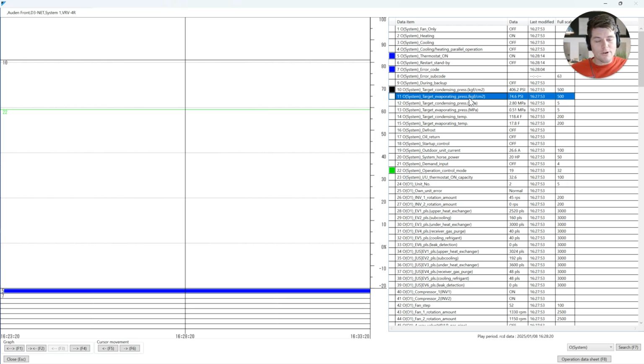Well, what about parallel operation, Roman? Well, guess what? Parallel operation, it all just depends on who is calling for what and what the demand is. If the demand for cooling is higher, it's going to use target evaporator pressure. If the demand for heating is higher, with that load split on parallel operation, it's going to switch over to target condensing pressure. How do we see this in a system? We can plot these two at the same time with parallel mode operation and watch it drive to one over the other. It's going to go to one. It's not going to go to both.